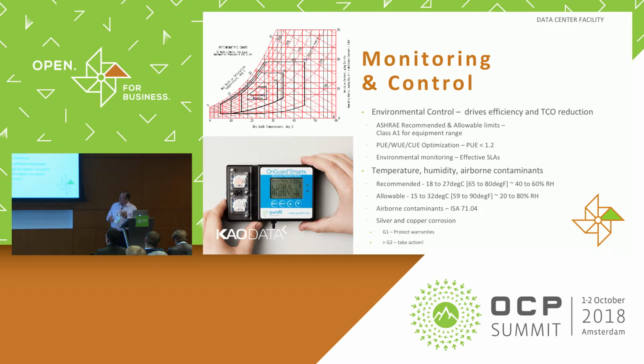We've got the ability to control to the ASHRAE recommended range, achieving a mean PUE of about 1.2. But what we like to do is talk to our customers and get them to work within the allowable range. We heard from John Levan this morning about OCP servers being quite happy to take 40 degrees in. So within the UK climate, we're probably talking about 3 hours a day within 10 days in 3 months worth of weather where we're going to exceed about 27 degrees. It's very important to understand what equipment we're putting in there - is it legacy, is it all OCP - and then we can help choose the envelope that people work to. We can achieve that, and all without refrigeration.